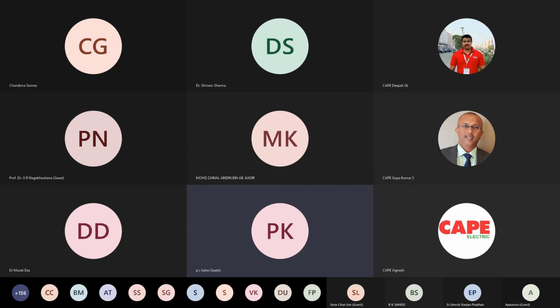Sir, what I'm saying is, does demography make any difference? I used to stay in Chicago. There used to be very loud thunderstorms almost every day. So, say upper hemisphere, northern and southern, the isokeraunic level can be very high, but demographically, I feel that you can specify which are the areas that need this kind of surge arrestor or lightning arrestor. For surge arresters inside residential buildings, you don't have to worry about these currents of 100 kiloamperes or whatever. A few kiloamperes will be more than adequate because the currents are due to indirect lightning, not due to direct lightning at all. You just don't have to worry about that.